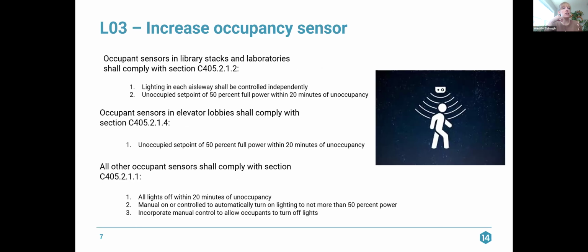So within section C405, there are a lot of different occupancy sensor requirements for different space types. Within credit L03, there are also explanations around how the occupancy sensors should be implemented in some of these specialty spaces. In library stacks and laboratories, you have to comply with the occupancy sensor requirements of section C405.2.1.2. That section requires that lighting in each aisleway shall be controlled independently. So, when you're walking through a warehouse with a bunch of aisles and the lights come on as you go down each aisle, that's what they want to see here in laboratories and library stacks.